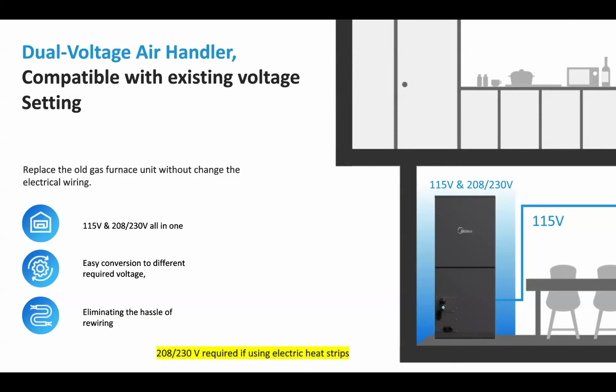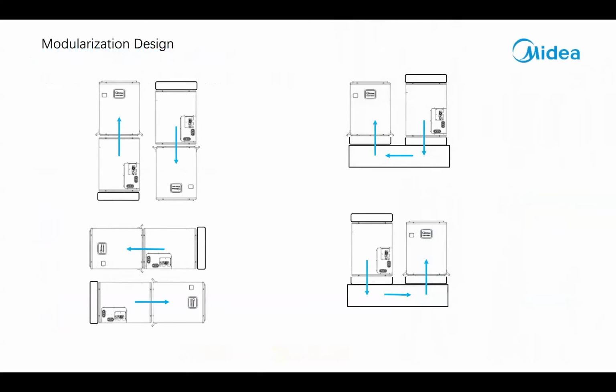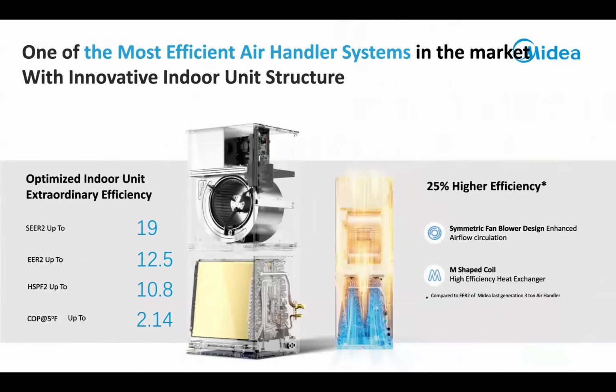You will have to use 208/230 if you're going to use electric heat strips. Back to the modular design: upflow, downflow, horizontal left, horizontal right, low boy left and low boy right. All right, so these are our numbers up to a 19 SEER, EER 12.5, 10.8 on your HSPF2, and 2.14 is your actual COP at 5 degrees. This system will actually produce 100% of its heat output down to -5.